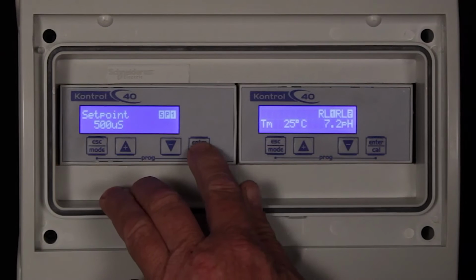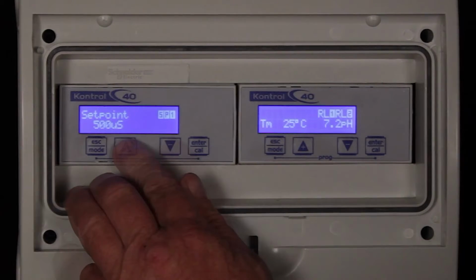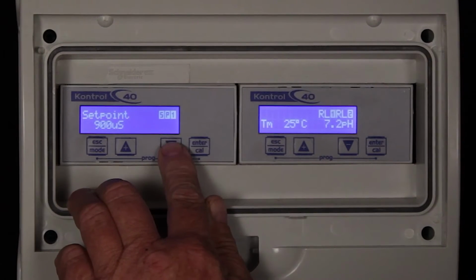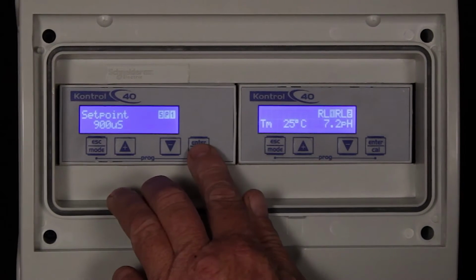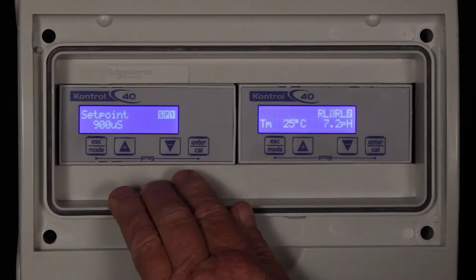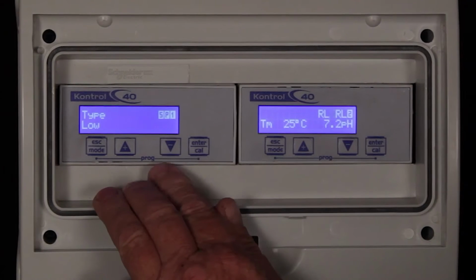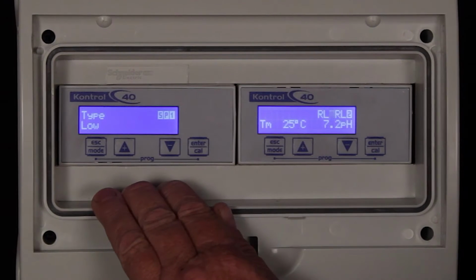Use the up and down arrows to change the value. For the purposes of this tutorial, I've set the value to 900 microsiemens. Now press enter again to return to the programming mode menu. Press the down arrow. The next parameter is the type of set point. The type of set point in this application is low, meaning that if the actual value is lower than the set point, the pump will turn on.